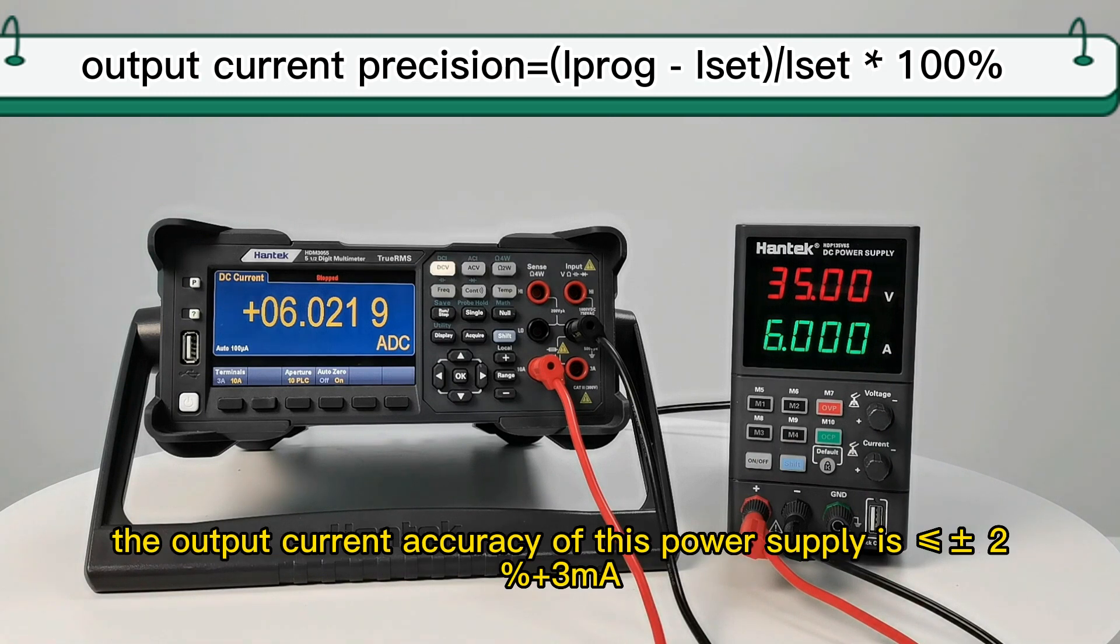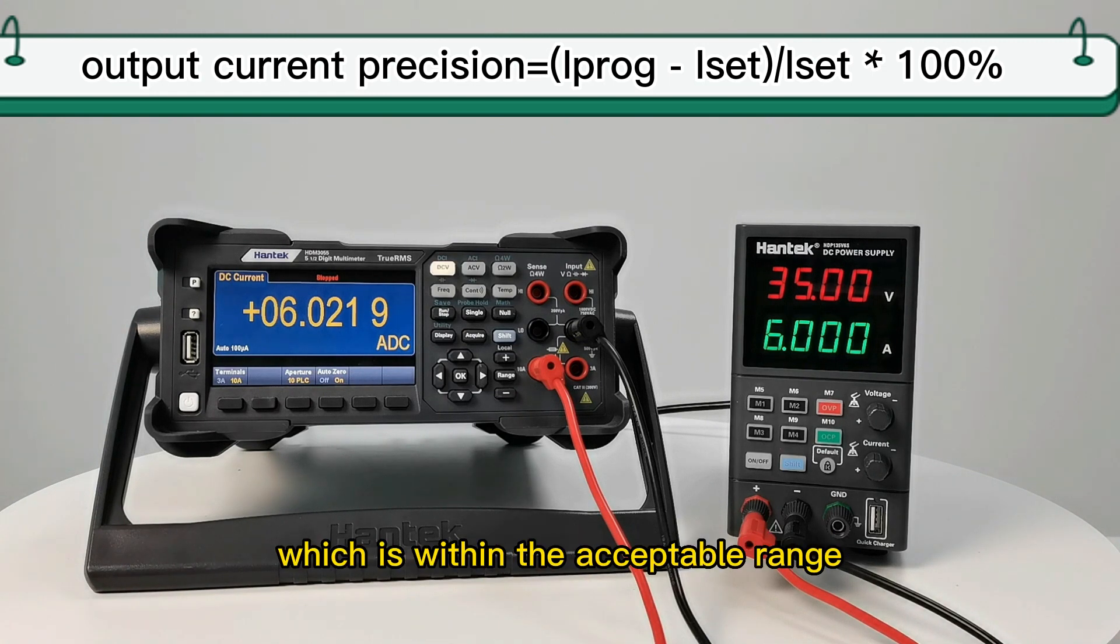From the results of several measurements, the output current accuracy of this power supply is ≤ ±2% + 3mA, which is within the acceptable range.